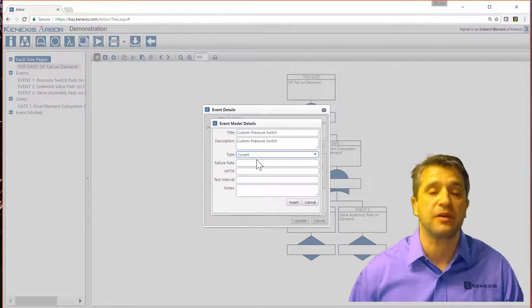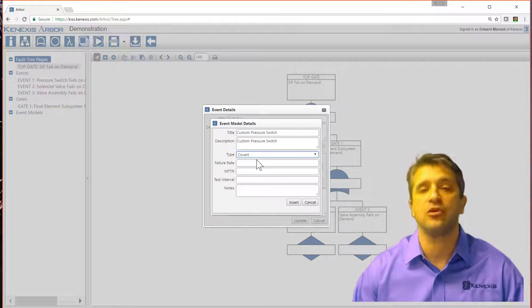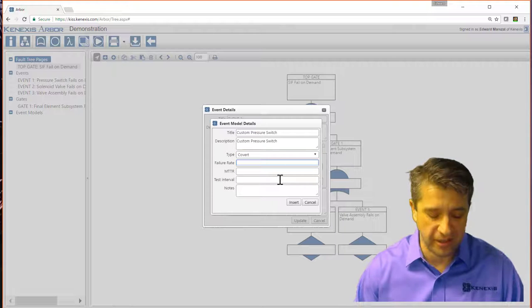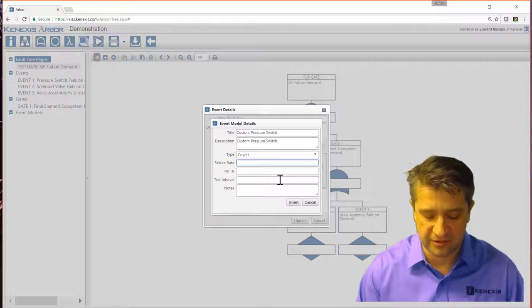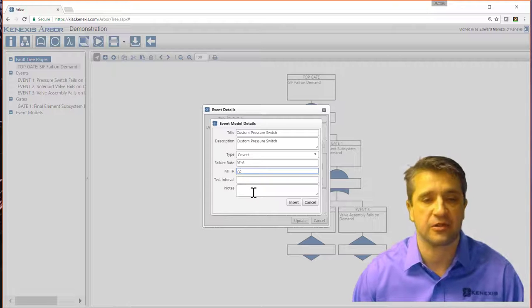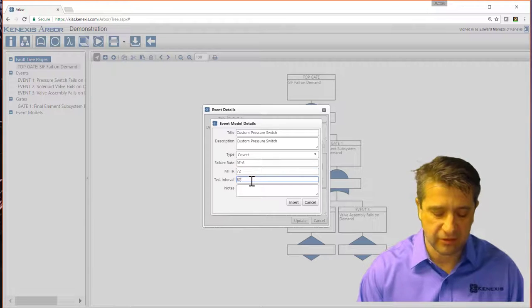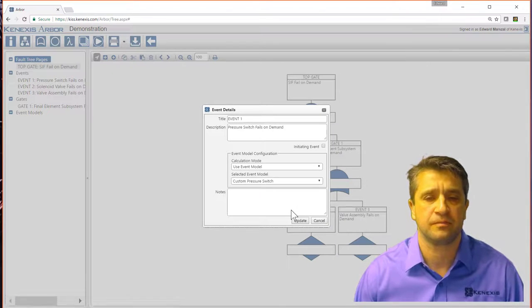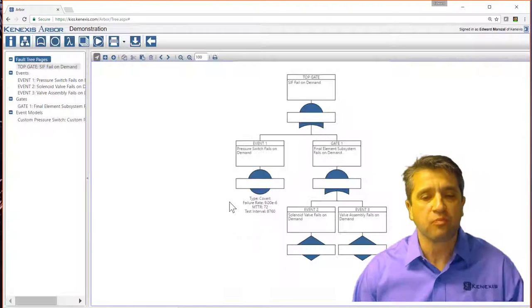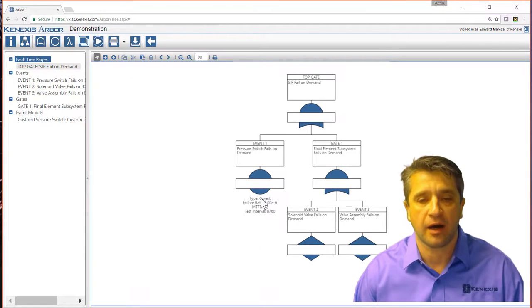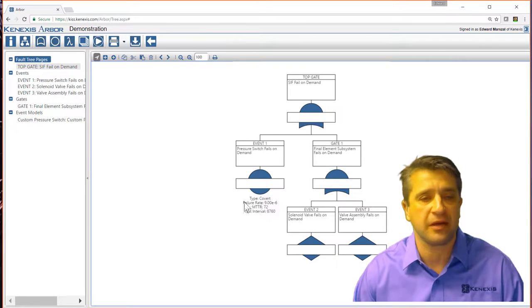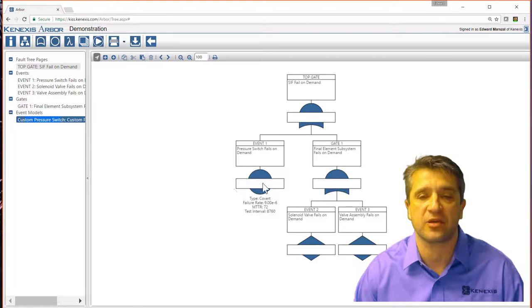For safety instrumented functions, when we're calculating probability of failure on demand, you generally use the covert model. Let's say the failure rate of this device is 9e-6 per hour. We can enter in a mean time to repair, let's go 72 hours. Test interval, let's just go once per year, 8760 hours and insert. And then I hit update. Now you'll see that that information about the event is loaded here, and the custom pressure switch model has also been loaded.